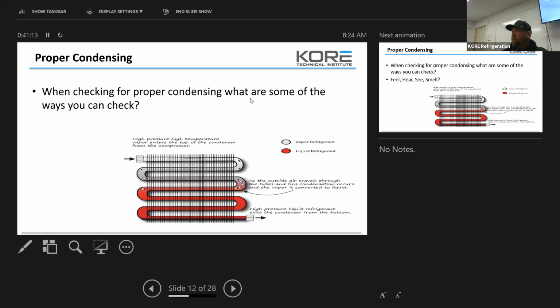So wash it again, or check your rotation, or check to make sure your belts aren't slipping. If you touch it and it's hot and it's bubbling, then you're not condensing properly. Make sense? So that's the easiest thing: just look at your sight glass, touch your liquid line, or touch your liquid drain leg. If you're dealing with small systems, run your finger down the return bends. That's how you can tell on a cap tube system if you're properly charging and condensing. So 2/3, 1/3, right? 2/3 hot, 1/3 condensed.